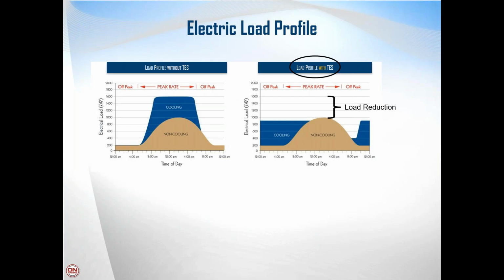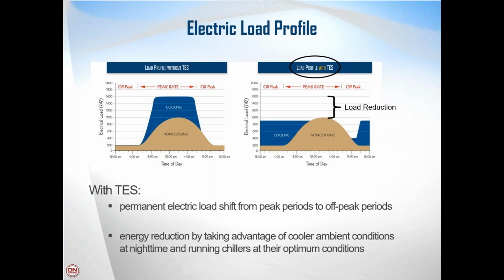If an owner were to add a thermal energy storage tank to their system, they could permanently reduce that electric load that they would consume during the day, because now they have the opportunity to run their high horsepower chillers and pumps at nighttime to cool that water, and then during the daytime they would have lower horsepower pumps pushing that water out to the campus for cooling, and they would be able to de-energize their chillers and cooling towers. So there's a permanent electric load reduction capability that they would see at their facility or campus.